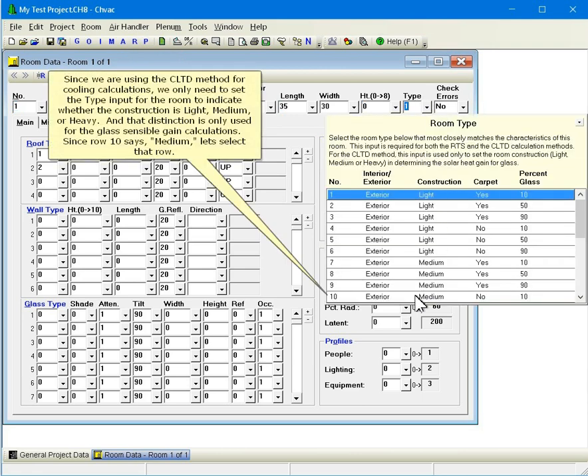Since we're using the CLTD method for cooling calculations, we only need to set the type input for the room to indicate whether the construction is light, medium, or heavy. And that distinction is only used for the glass-sensible gain calculations. Since row 10 says medium, let's select that row.